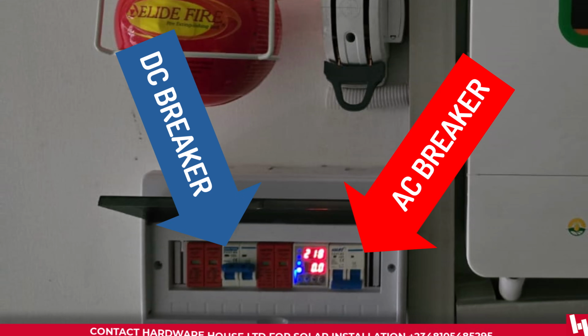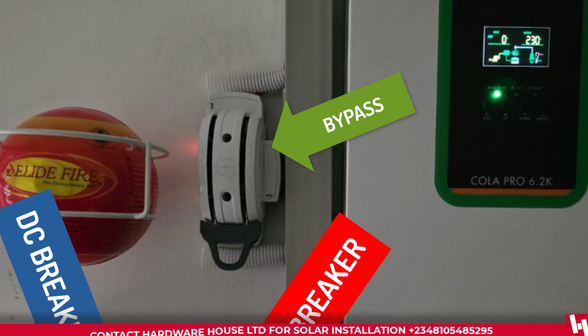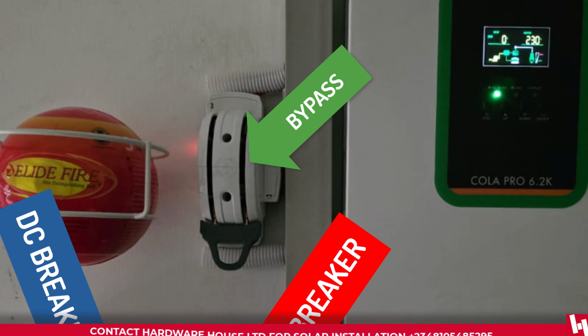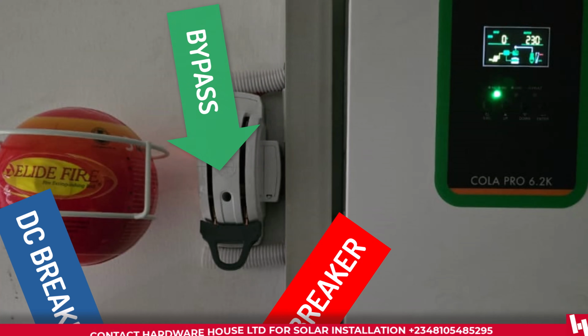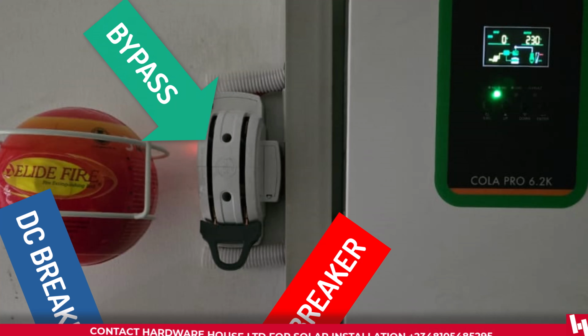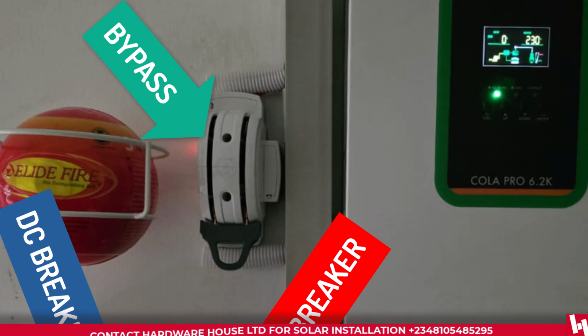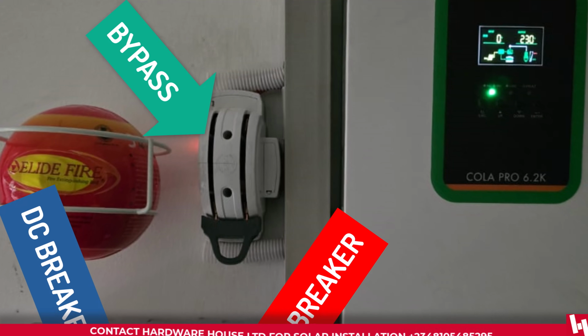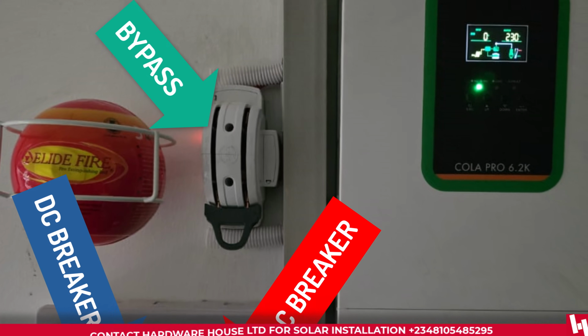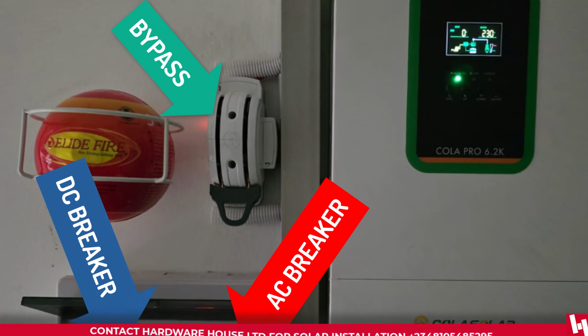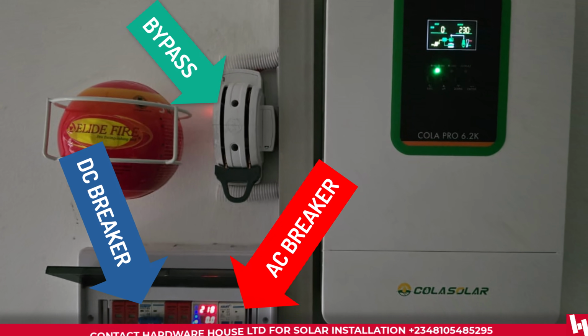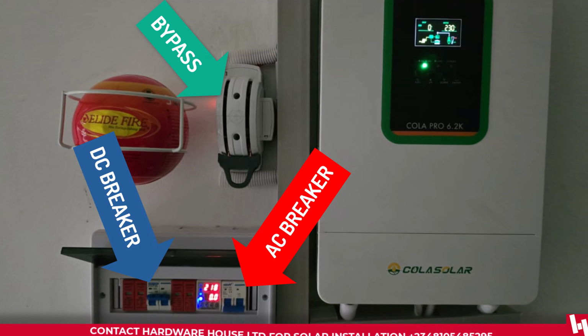Then we also have the bypass, the changeover switch that you see over there. That one helps to disconnect the house from the inverter system whenever you want to use just your gen or just your grid power to do other things that you don't want to power with the inverter system.